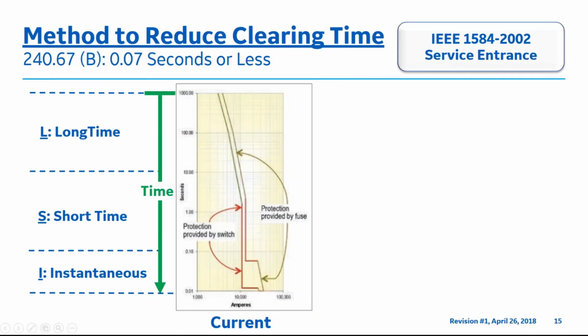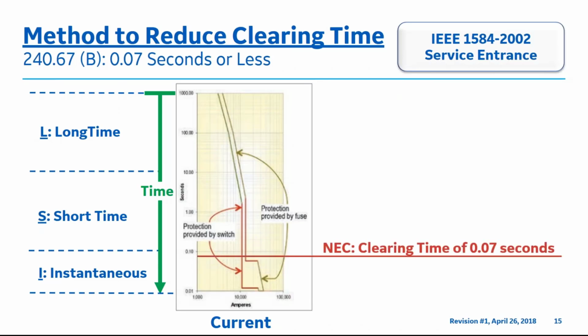Reducing the time component, which is labeled on the y-axis, is a key aspect to lowering the arc flash incident energy level. As demonstrated on the previous slide, the two 400 amp fuses with the 10-foot cable length versus the 600-foot cable length had different arcing current clearing times. As the NEC is specifying an arcing current clearing time of 0.07 seconds or less, this red line represents the specific clearing time in the instantaneous region of the time current curve by the new 240.67 NEC code.